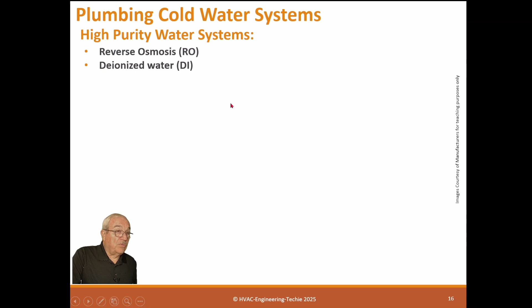So we have storage tanks in the system, we have filter systems, we have pumps, and it's normally used for clean water for cleaning or consumption, and for manufacturing processes that require very clean water. So RO, most restaurants use RO water for their drinks. Alcohol beverage tastes much better if the water in is pure. And also for drinking water, when you go into a restaurant most of the time, the water tastes really good because it's right out of an RO system.